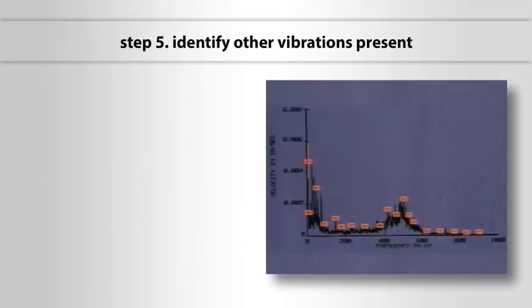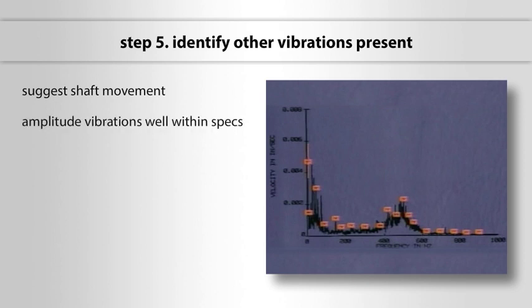Step 5: Identify other vibrations present. When we mark the one-times with the cursor, the analysis software automatically identified several harmonics. This would suggest shaft movement, but remember, these are tiny, low-amplitude vibrations, well within specs.